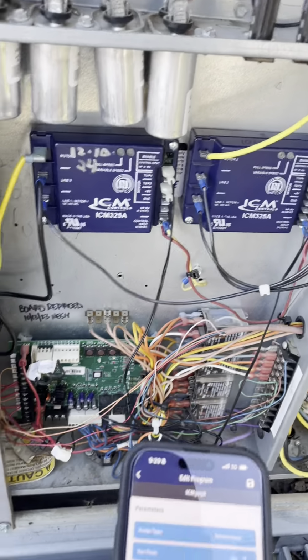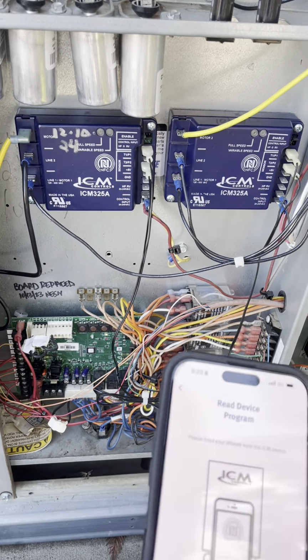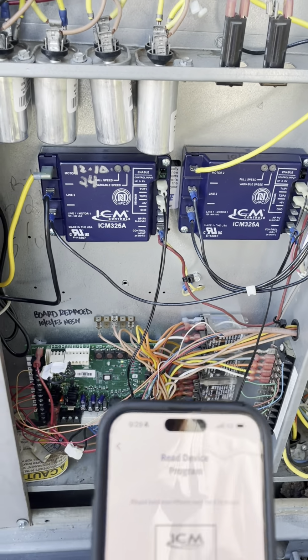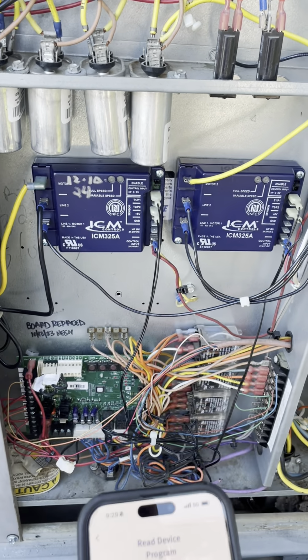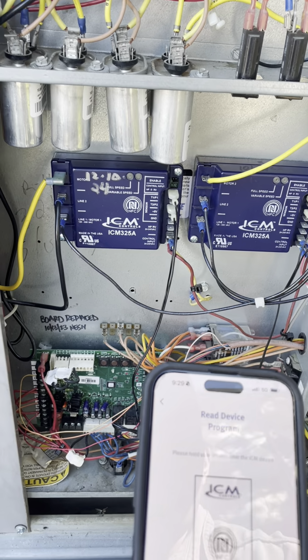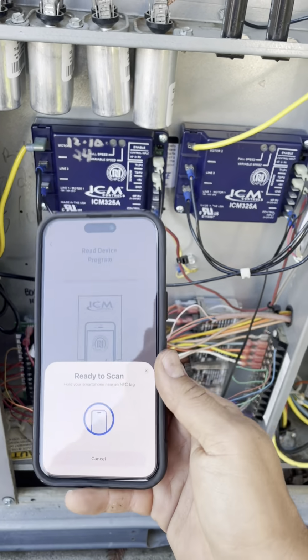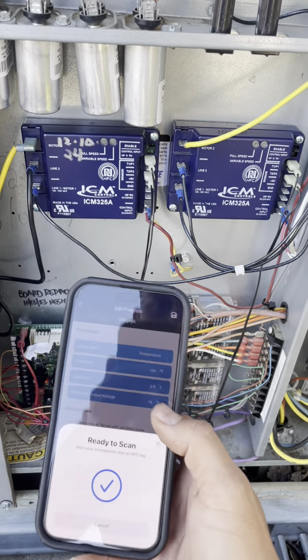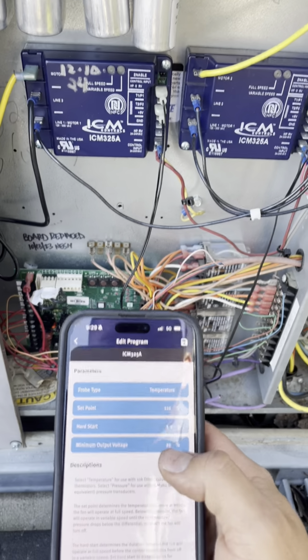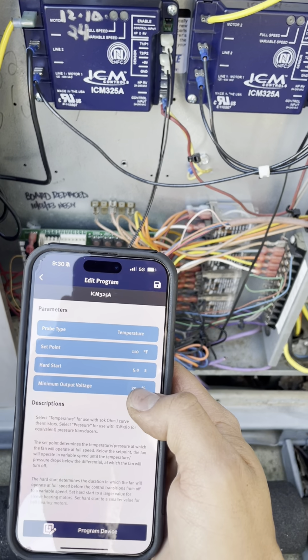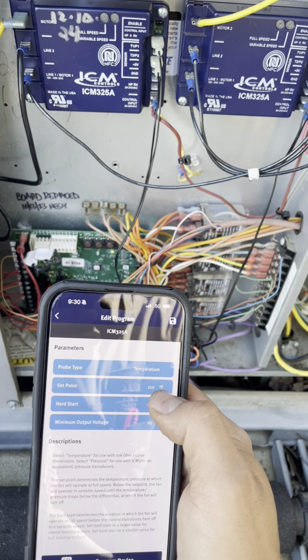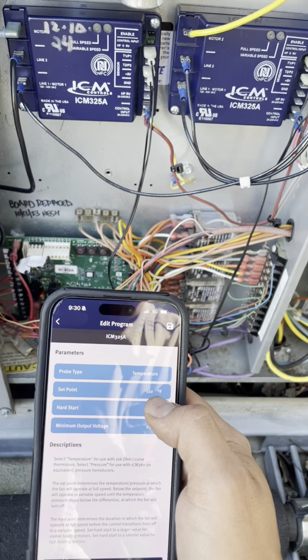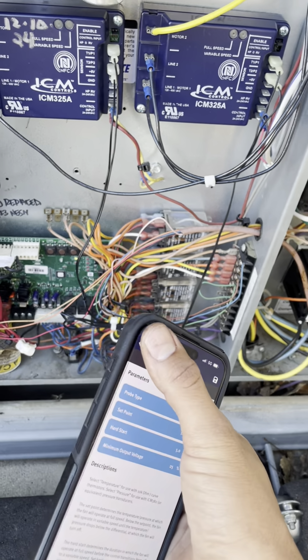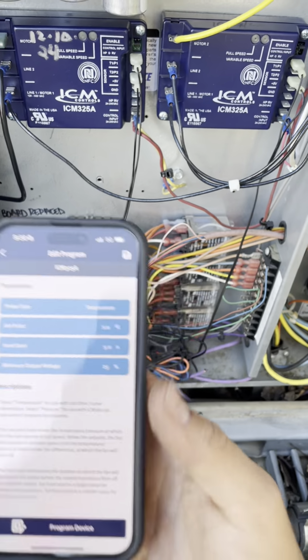Okay, I just learned something. These ICM control modules have an app. I had no idea. I called my foreman because I was kind of at a loss for what to do here. He told me to check these control modules because he just learned about it too. And you download the app and you can scan this little NFC tag, and it tells you what the set points are. You can set the minimum output voltage in the variable speed mode. And more importantly, you can change the set point of what this thing's trying to maintain. These were set to 100, so I bumped them up to 110. So you can make adjustments, and then you tap it again and it programs the controller. I think that's freaking cool.